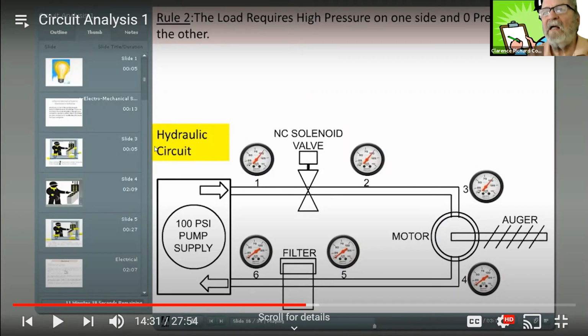Okay, now we got the solenoid valve switch turned on. The auger motor does not turn. Gauge 1 is 100, and everything else is 0. So the choices are: the motor's bad, there's a restriction between 2 and 3, or a restriction between 1 and 2. 92% of you got that.